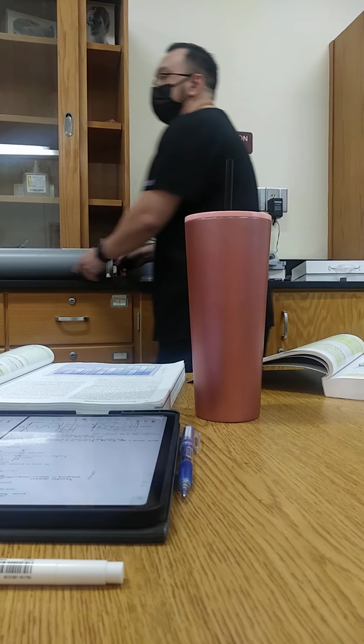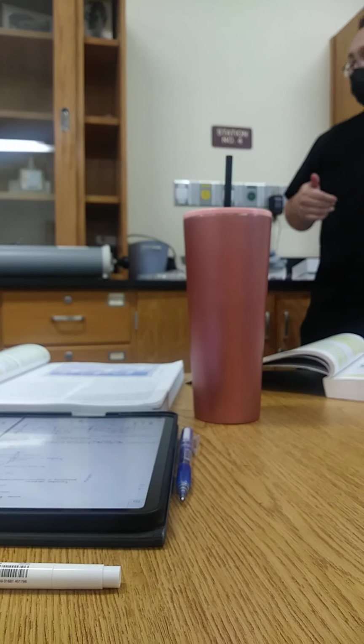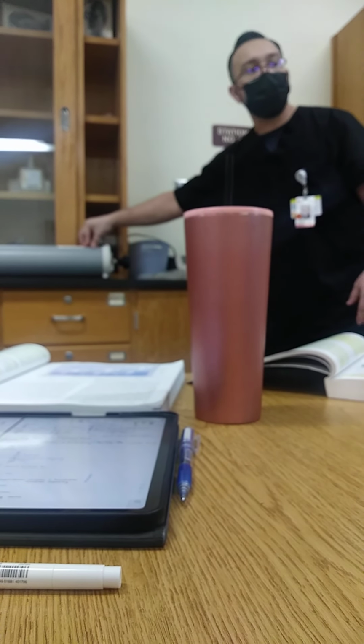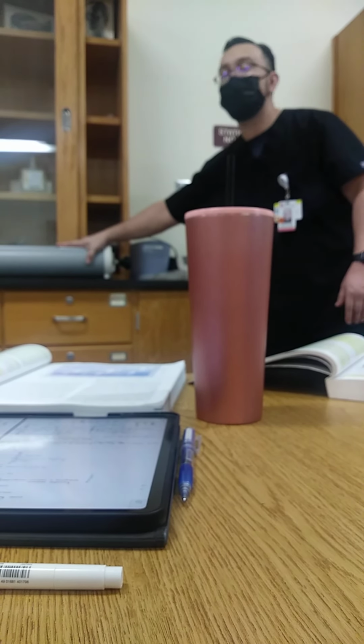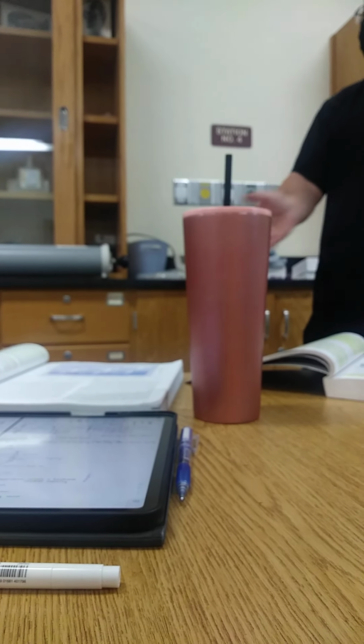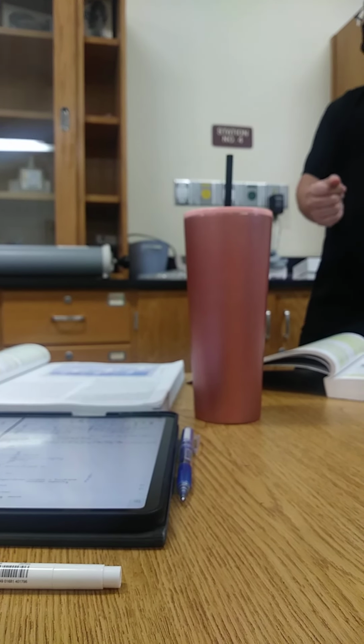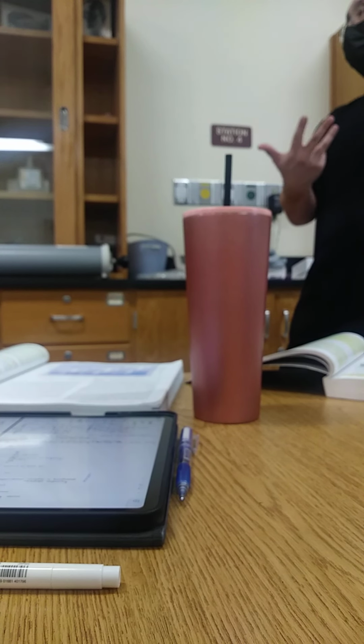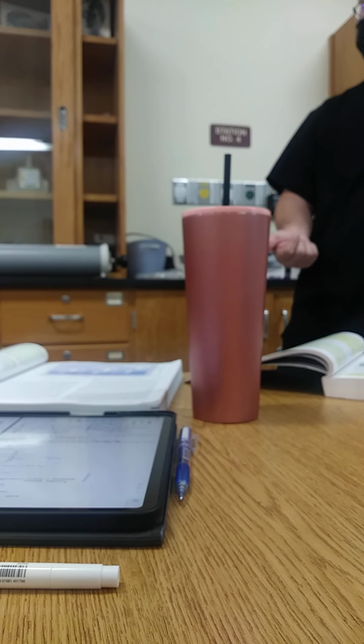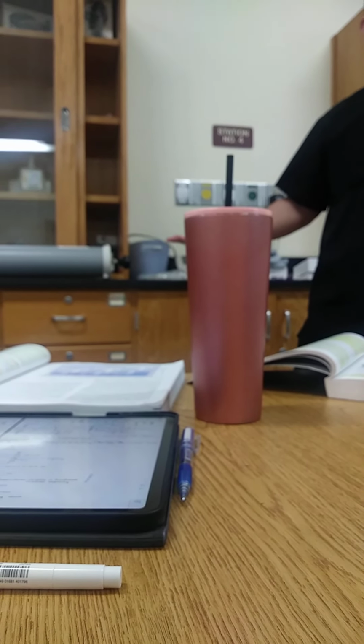Remember, and we'll get into this more next week, but 3 liters becomes important. This is made with that amount of volume. So if you push it in like you're supposed to with your device and you get 3.5, where did that extra volume come from? Or you get 2.5, where did that extra volume go? And so that's what's going to alert you to issues, okay?